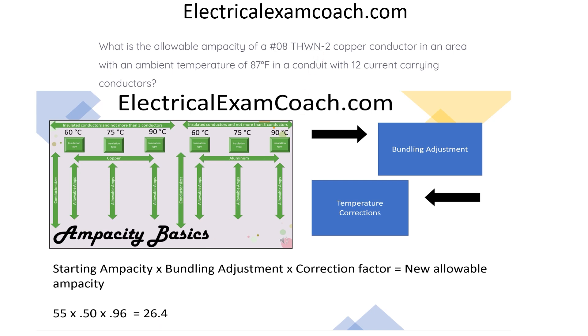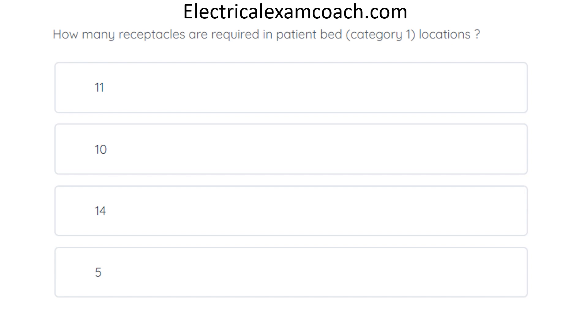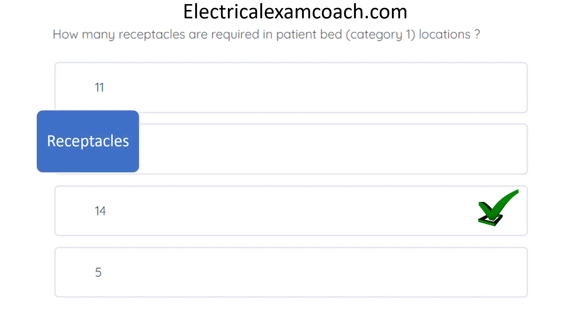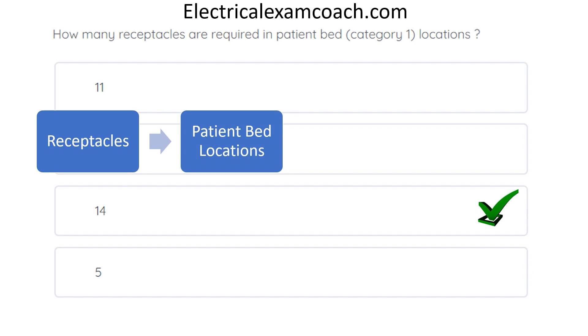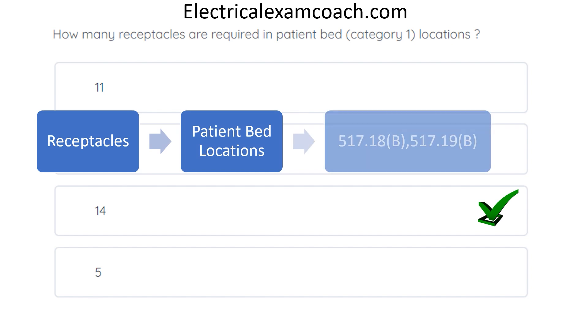How many receptacles are required in a patient bed category 1 location? The correct answer is 14. There are 14 required receptacles in this category 1 location. To find it, we use our keyword and index process. We're talking about receptacles in patient bed areas, so we go to R in the index, then look for patient bed locations in the index. We find two code references: 517.18(b) and 517.19(b).